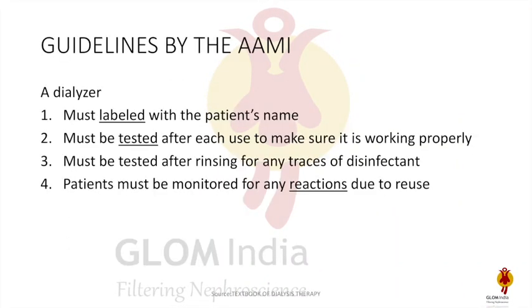As per the guidelines of the Association for Advancement of Medical Instrumentation, the dialyzer must be labeled properly with the patient's name, registration number, and other details. It must be tested after each and every use to make sure that it is working properly and does not contain any trace of disinfectant, and the patient must be monitored for any reactions.